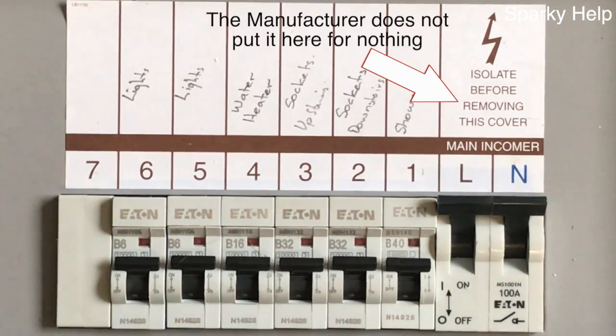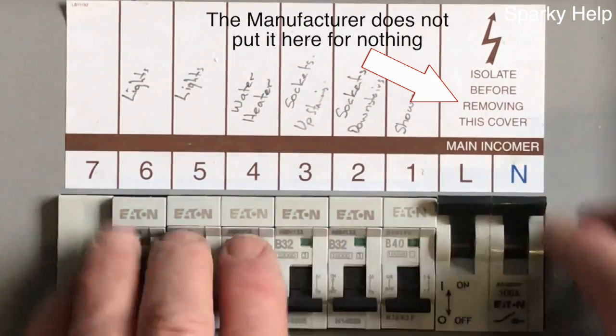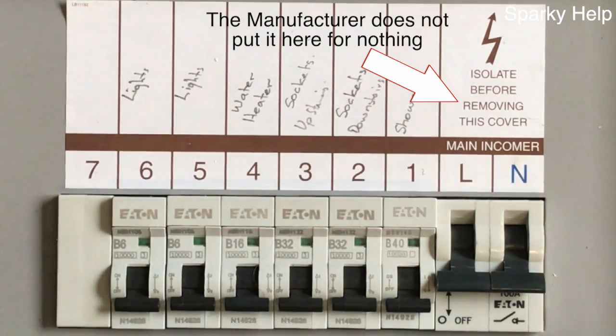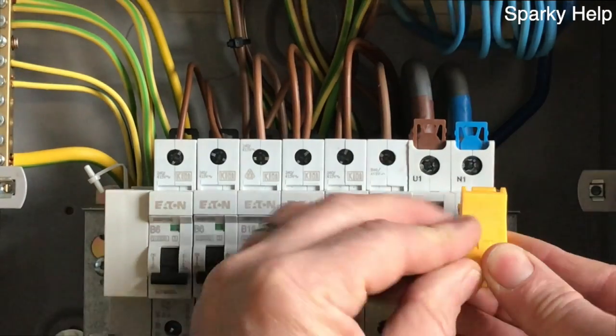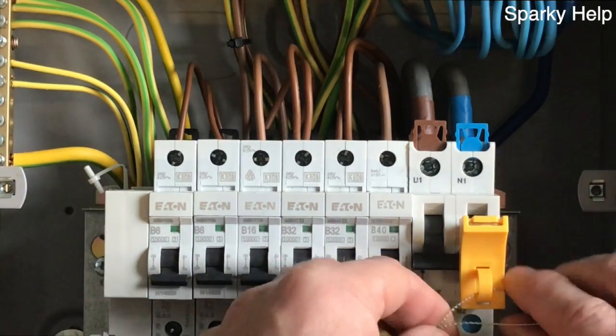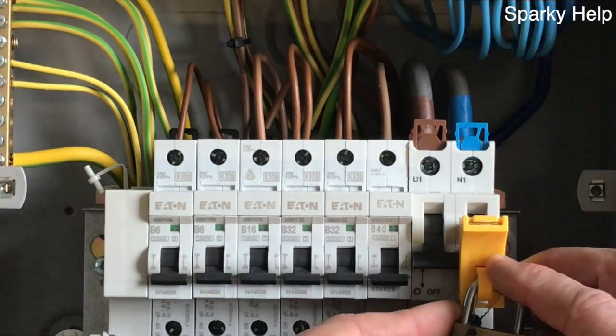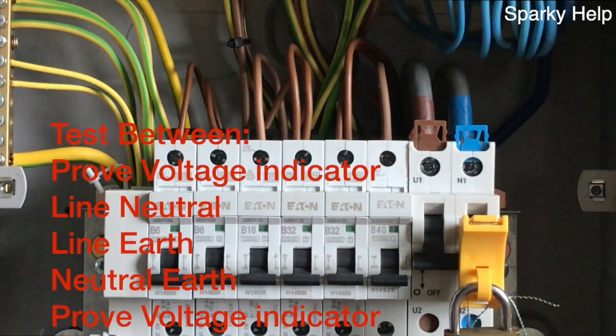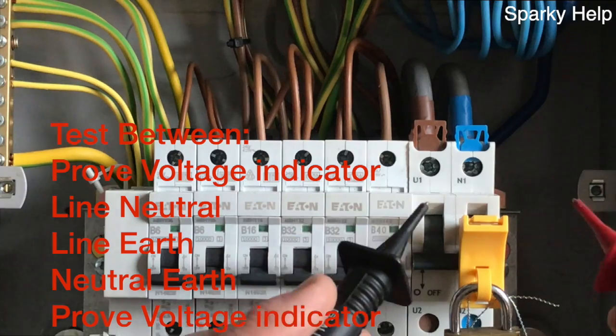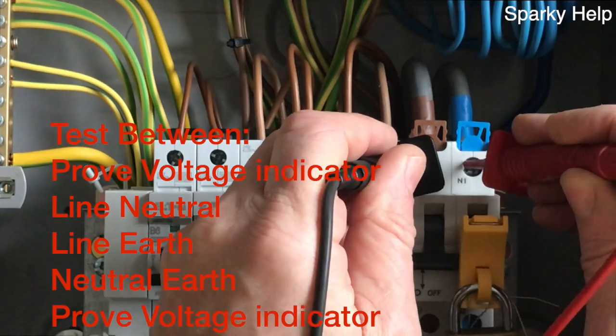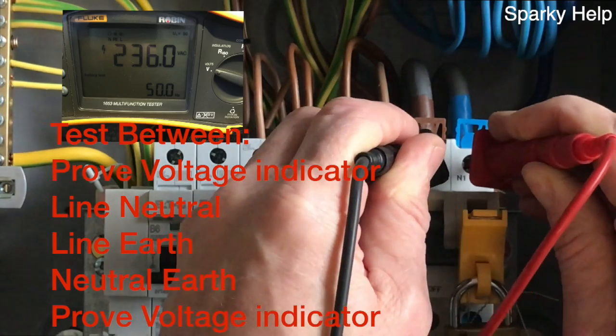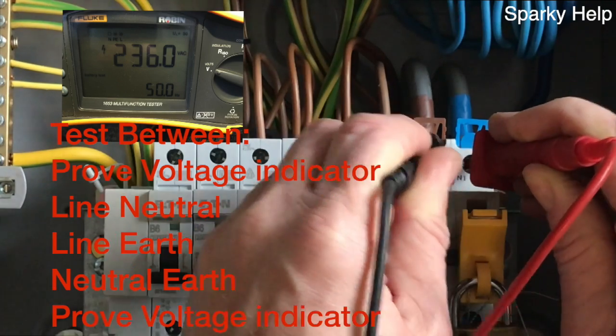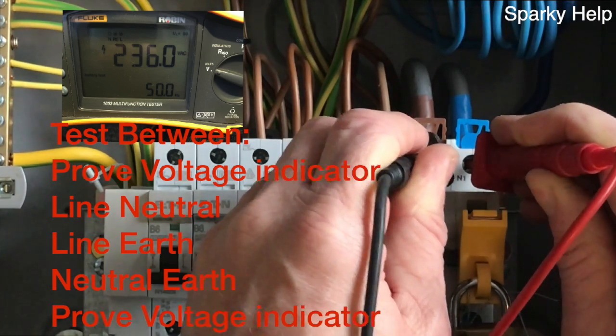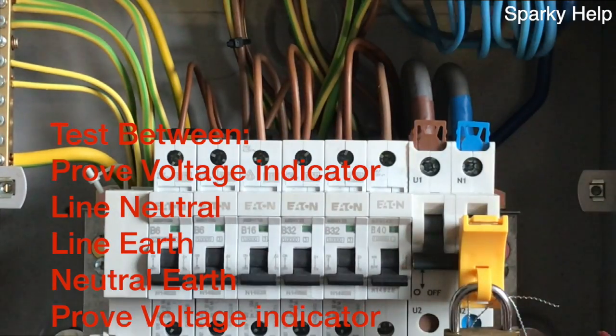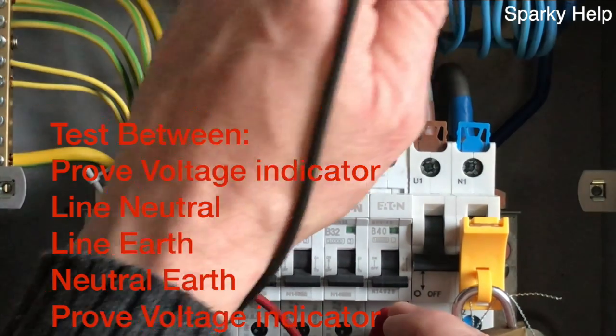So first things first, we get permission. Let's turn the board off before removing the front cover. I've already checked my testers on a proving unit. This side is going to be live because it's the incoming supply, so we can definitely prove our supply on here. This is coming up as 230 volts. But we want to go on the output side to make sure that is dead.